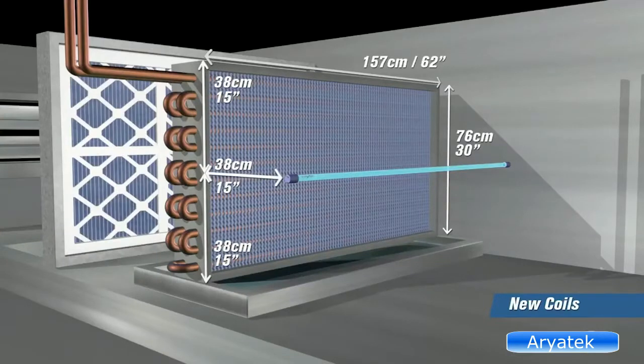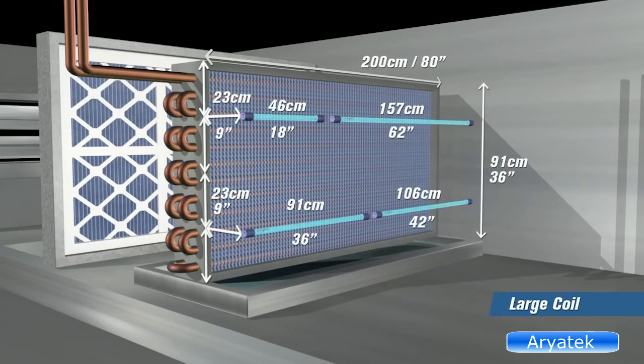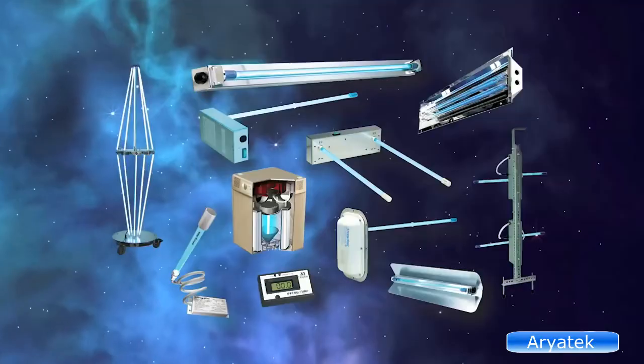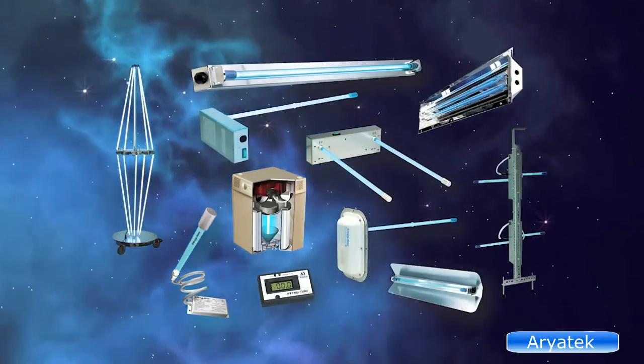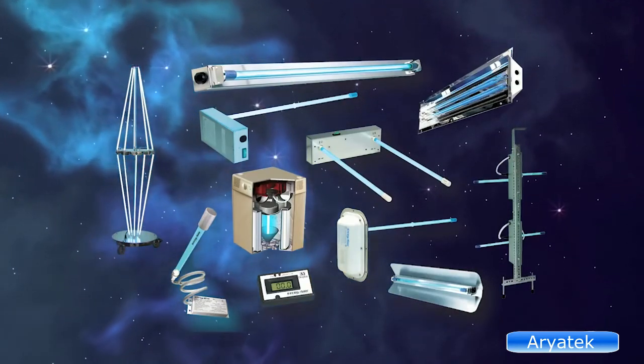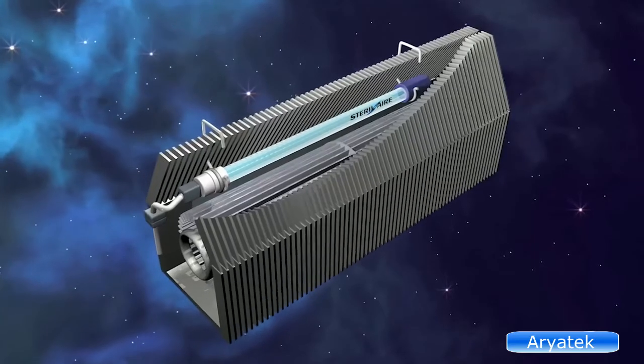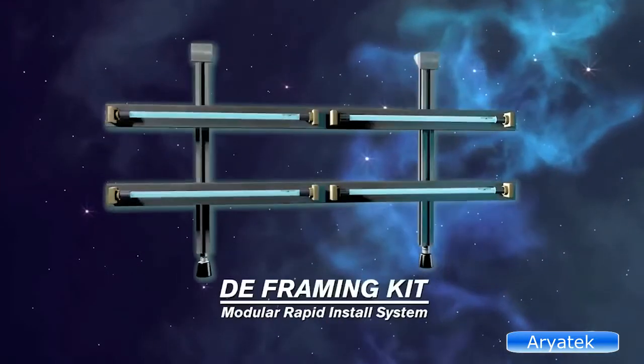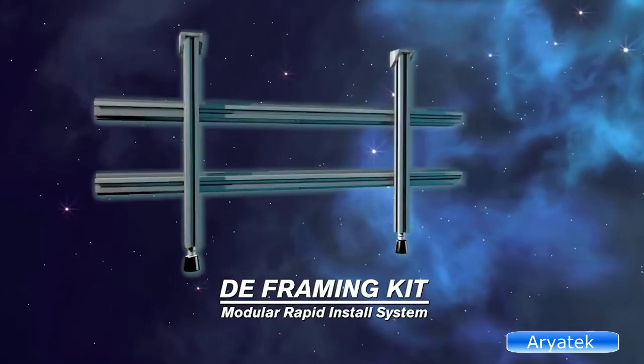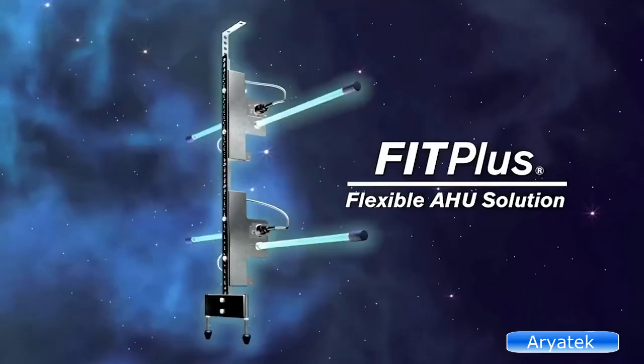To maintain a minimum UVC dose on a new coil, and to keep the coil clean, we recommend using one horizontal row of SterilAire across the full coil face for every 30 inches, 76 centimeters, of vertical coil height. In hospitals and existing coils, use one row every 24 inches, 60 centimeters. For bigger coils, add rows and emitters. SterilAire system-engineered, high-quality UVC family of products can be installed in the largest AHUs or the smallest splits and cassettes. For ease of installation, we provide rapid install modular framing systems and the FIT, fast install tower.